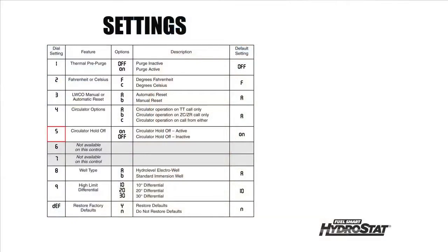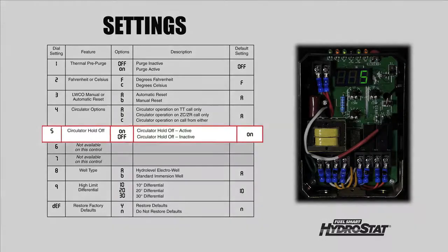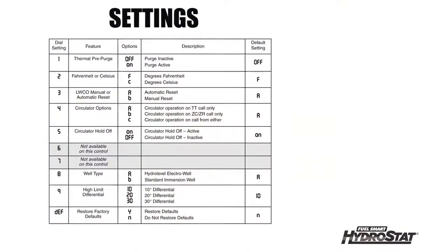Option five is called circulator holdoff. This option is used for cold start applications and provides for holding the circulator off on a call for heat until the boiler temperature reaches 125 degrees Fahrenheit. This allows the boiler to heat up faster and minimizes the time the boiler is operating at a temperature in which flue gases will condense.